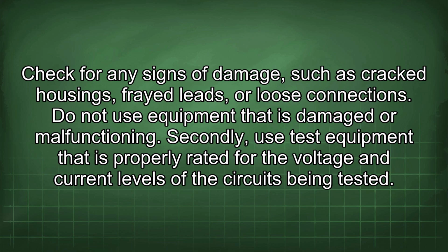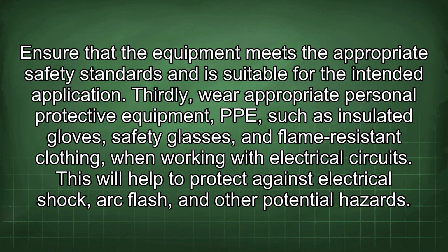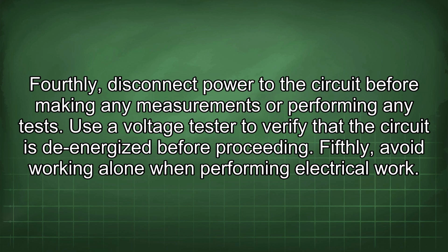Secondly, use test equipment that is properly rated for the voltage and current levels of the circuits being tested. Ensure that the equipment meets the appropriate safety standards and is suitable for the intended application. Thirdly, wear appropriate personal protective equipment, PPE, such as insulated gloves, safety glasses, and flame-resistant clothing when working with electrical circuits. This will help to protect against electrical shock, arc flash, and other potential hazards. Fourthly, disconnect power to the circuit before making any measurements or performing any tests. Use a voltage tester to verify that the circuit is de-energized before proceeding.